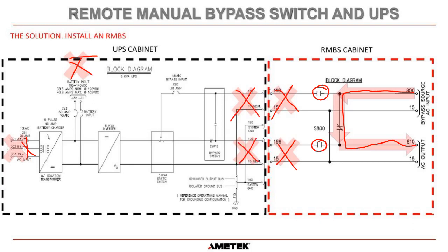So now we have isolated all power from the UPS cabinet itself, and a technician can go in and do intrusive work on this UPS, safe in the knowledge that it is locked out, tagged out, and there is no energy or stored energy inside this UPS now. Obviously, you'd have to wait for the DC capacitors to discharge themselves. We have self-discharging resistors on our DC capacitors, and that takes about 2 to 5 minutes. But now you can go in and work.